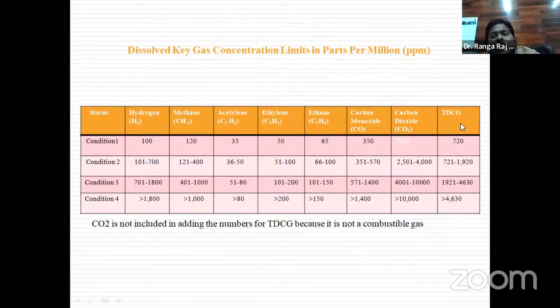For the different gases like hydrogen, methane, and ethylene, if you sum them all up, that gives the total dissolved combustible gas, TDCG. Based on the TDCG value, we can decide the overall health condition of the oil.